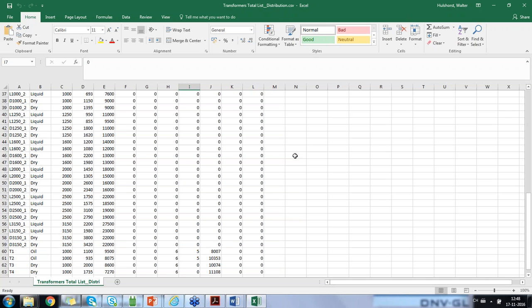It is not the case in practical application. The current harmonics which the transformer is catering to may vary depending on what node it is catering. So there can be enormous variation. As far as voltage harmonics is concerned, there may not be any voltage harmonics, or there may be voltage harmonics which is inherent and which will be very low magnitude. So we really regret that there is no specific answer to this question.